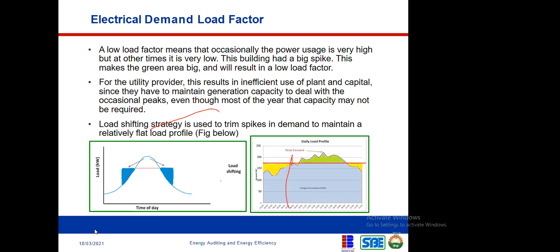Let's go to the next. So this is just an example to make us understand the load factor. Compute the monthly load factor when peak is equal to 1,250 kilowatts. Energy used is 500,000 kilowatt hours. Of course, then time is 720 hours, 24 hours per day, and 30 days per month.